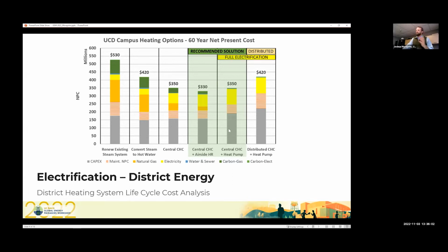Every other option here uses hot water. The big question for us, as Berkeley also looked at, was whether to go with distributed plants or a centralized system. The argument for distributed plants, when you have a chilled water system, is that you already have this heat collection system—why put in a whole new distribution piping system if you could tie in local heat pumps to that chilled water system and extract heat where you need it?